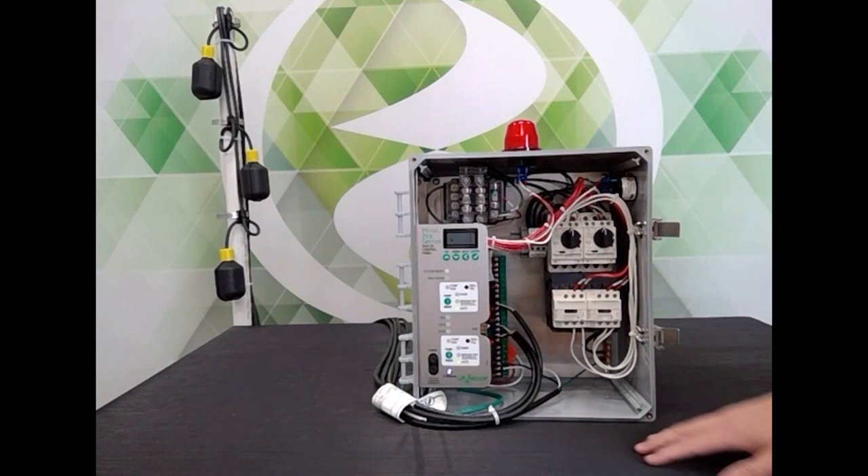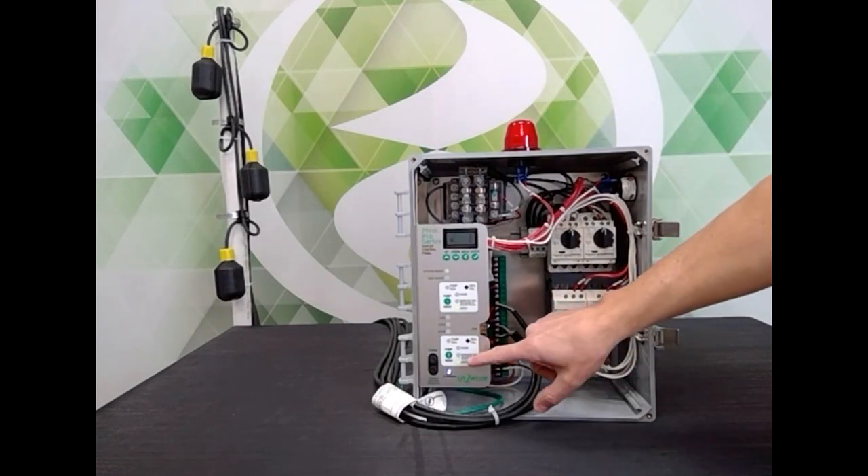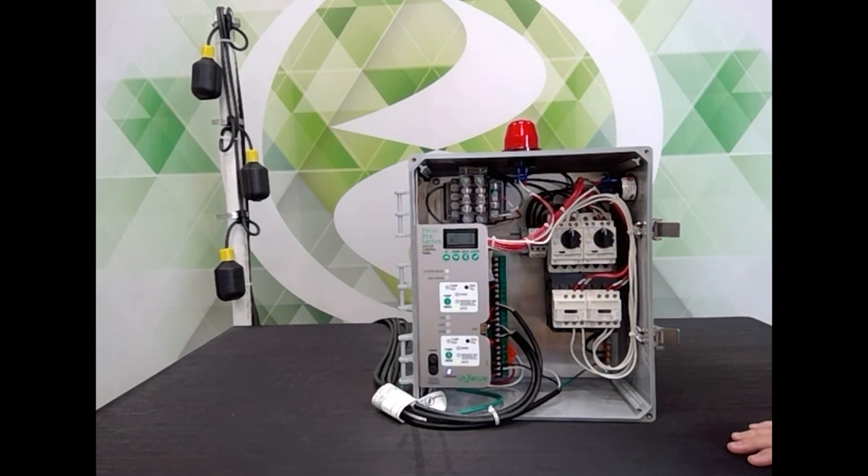The other is the off position, where by default after four hours, if you have it in off, it'll create an alarm. It's not going to put it back into auto for safety reasons — it's going to keep it in off. But at least you're going to get an alarm after four hours just in case somebody forgot.